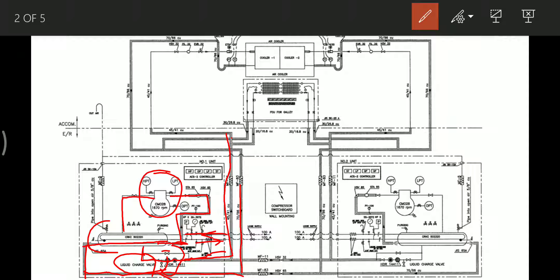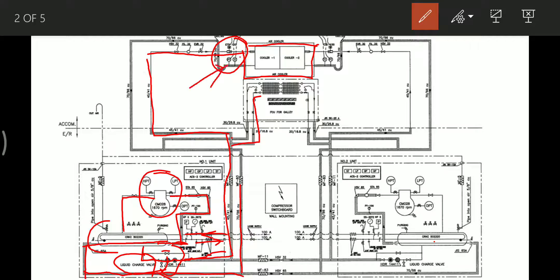After the filter and dryer, the refrigerant line divides into two parts: one section goes to the small evaporator for the galley only, and the other goes to the accommodation air handling unit. In the air handling unit, the cooler is the evaporator. The expansion valve here is electronically controlled — it receives signals from a temperature sensor and a pressure sensor installed at the outlet of the evaporator.